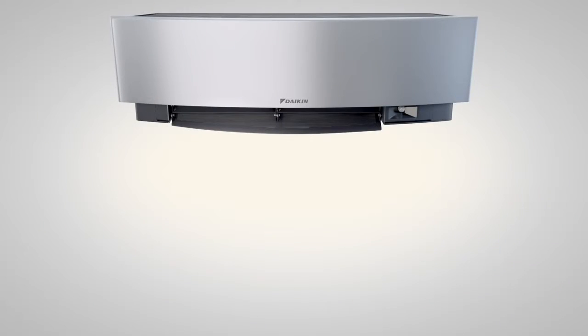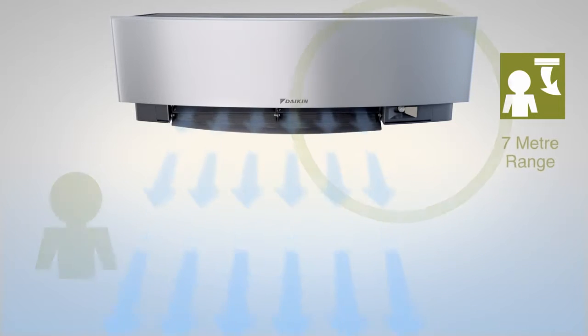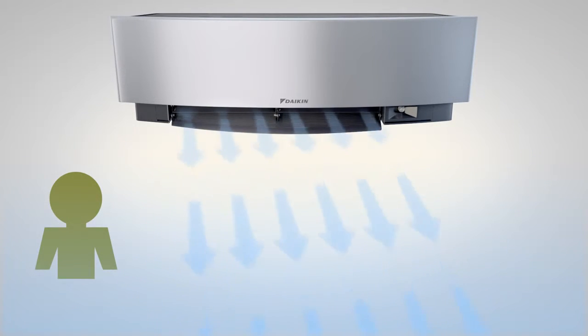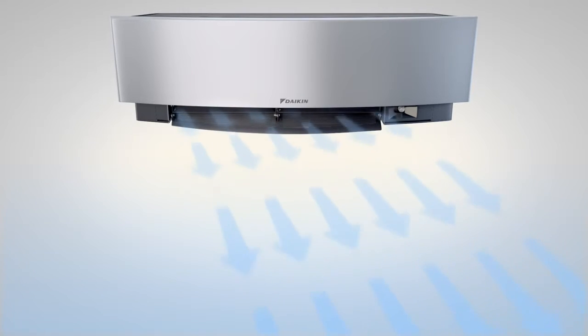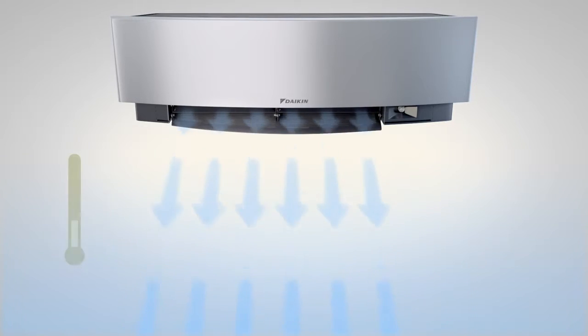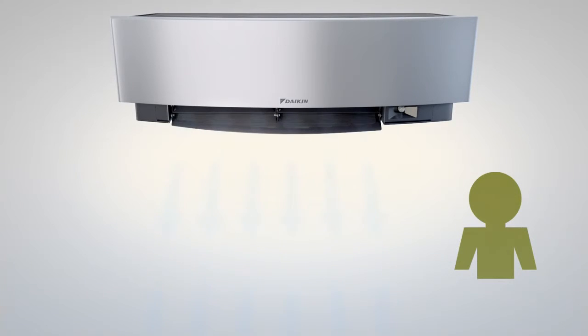A key innovation is Emura's intelligent eye, which uses sensors to detect human activity and direct the airflow away from people in a room to avoid cold drafts. If the sensor does not detect activity for 20 minutes, it will switch to economy mode. This changes the set point by 2 degrees centigrade — up if cooling, down if heating — to save energy, and returns to the original set temperature when the sensor detects someone re-entering the room.